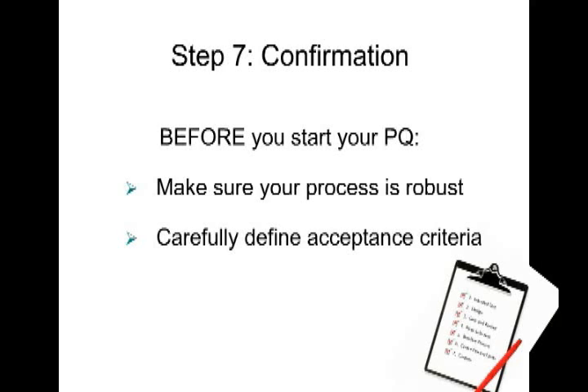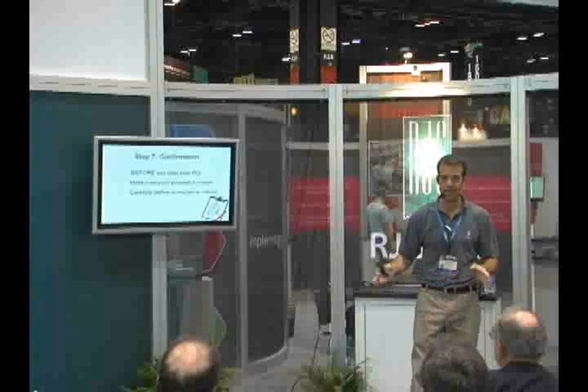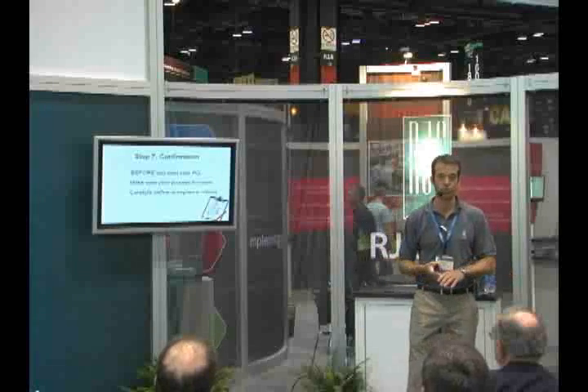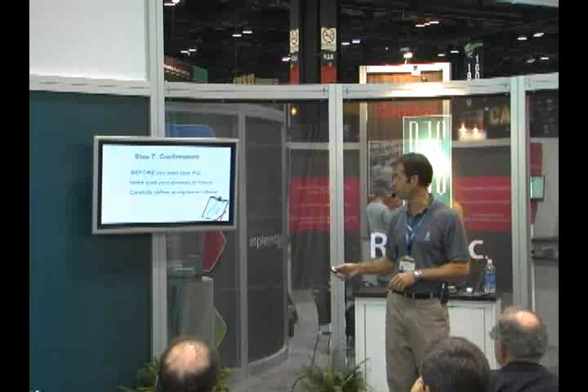We need to make sure that we've developed the OQ phase correctly so that when we get into the production qualification, we're not trying to make continuous adjustments to that process. We get everything squared away, we center our process in the OQ, and our PQ is then our 8-hour or 24-hour run, whatever the case may be.